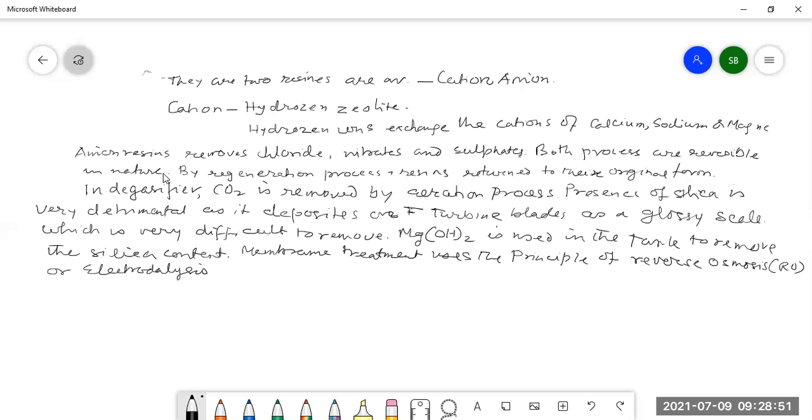In an osmosis process, liquid from an area of low salt concentration moves naturally through a semi-permeable membrane to an area of high salt concentration, where no external pressure is applied. The flow can be reversed by applying external pressure on the high concentration side. This phenomenon is called reverse osmosis. In reverse osmosis, dissolved salts are separated from water by forcing the water through the semi-permeable membrane under high pressure itself.